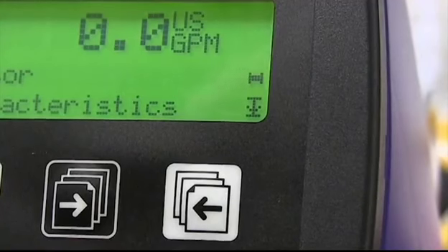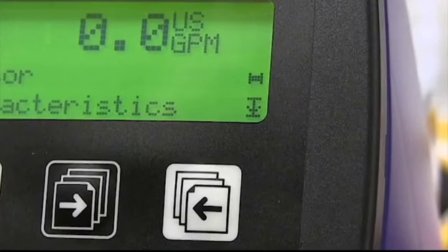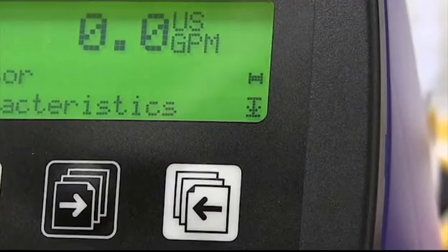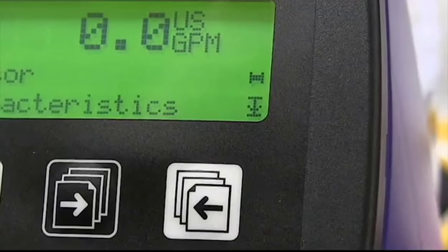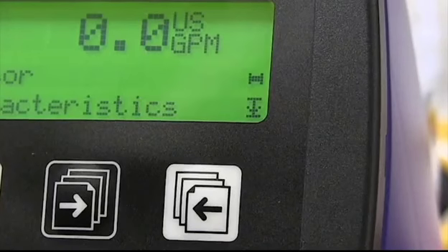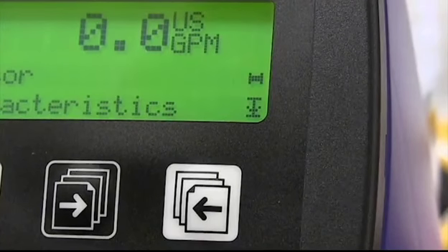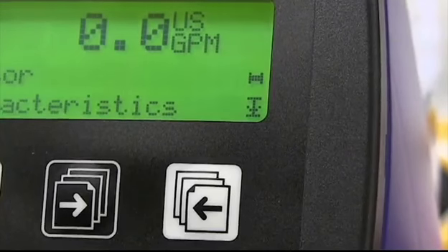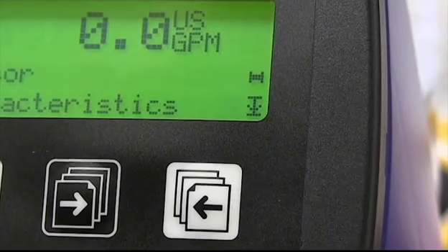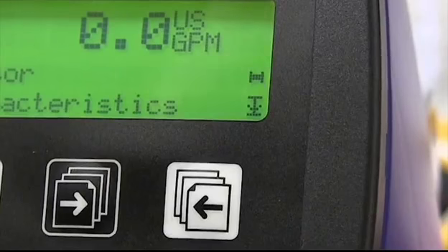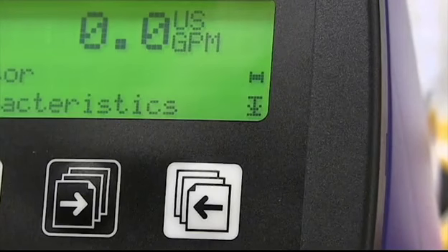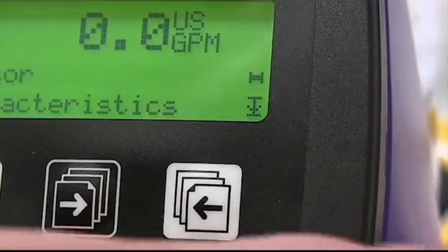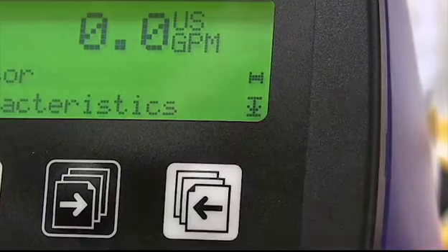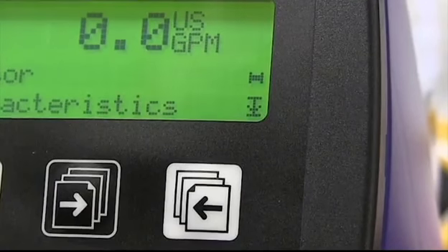You get to outputs, external inputs, sensor prom characteristics. This is where all the information from that sensor prom resides. So if we go down into these additional pages, you will find that your cal factor has already been entered, flow meter size and things of that nature. You'll also notice there's something in here that will say your sensor prom is installed. If for some particular reason a flag appears in this area during normal operations, like a square with a line going through it, that's an indication that something is wrong. In order to find out what that is, you would continue.